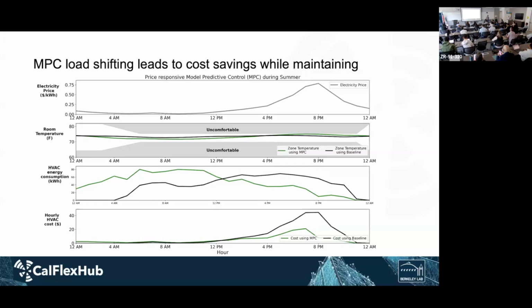And you can see that the MPC, starting pretty early in the morning or even at night, will start to do free cooling and pre-cooling, slowly dropping the temperature in the building. And in fact, you can see it also from the first chart where the consumption increases. And then after 2 p.m., the MPC starts to slow down the fans, slow down the cooling coils, so that the consumption will reduce. Of course, the temperature will increase, but because of the forecasting capability of the MPC, it doesn't go outside the comfortable boundary.